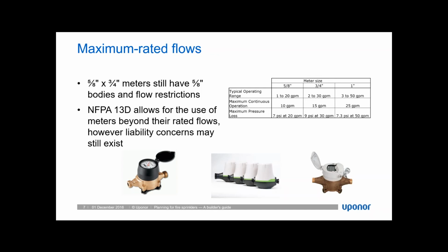The possible risk that's involved in exceeding the flow of a 5/8 meter mostly comes in the extremely unlikely event of a system failure. In the event of a system failure where some tragedy may occur, an investigation will likely take place, and something like the meter being designed outside of its maximum rated flow could be considered a factor in that system failure. So it should be very heavily weighted when considering the risks of moving forward with a design that exceeds the rating of your water meter.